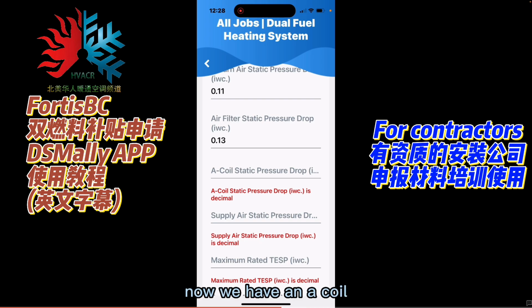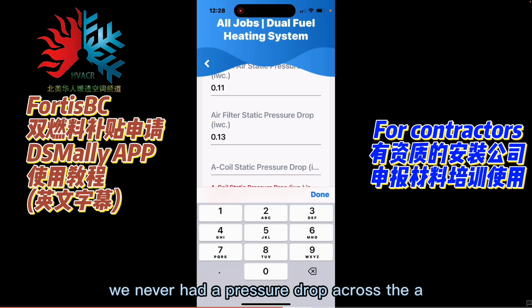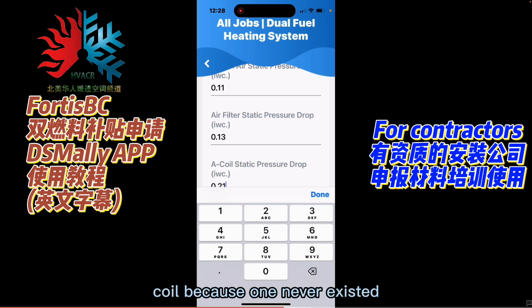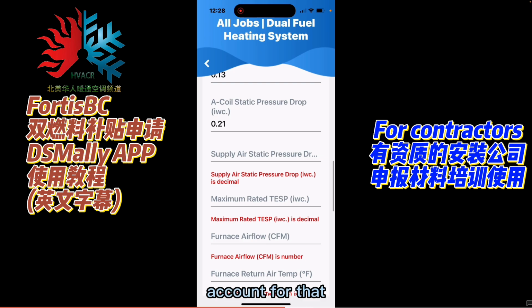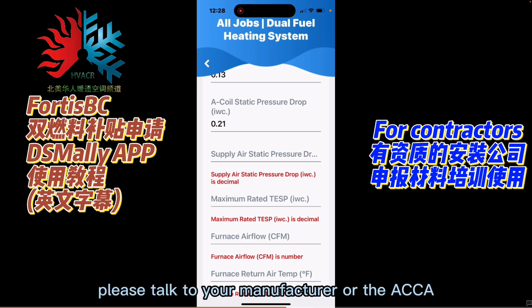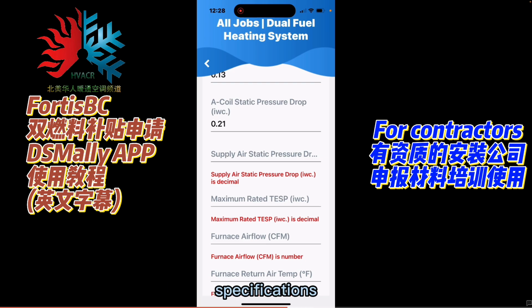And now we have an A-coil. So when it was furnace only, we never had a pressure drop across the A-coil because one never existed. So now you've got to account for that. Please talk to your manufacturer or the ACCA specifications on what the before and after on that pressure drop is.